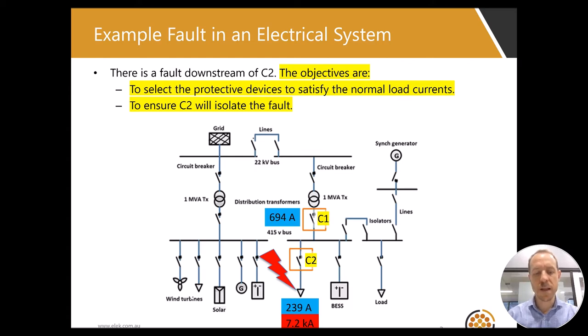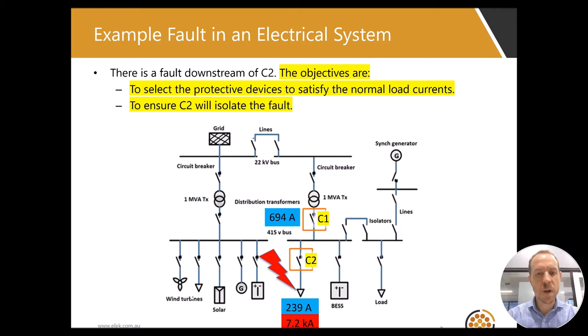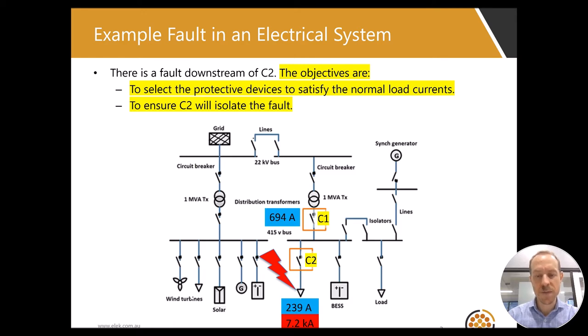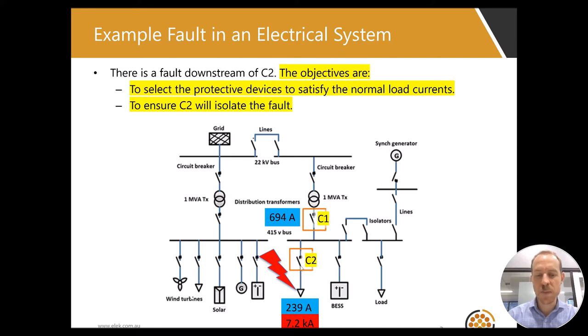Here is a schematic of an electrical system. In this example, I will focus on the selection of circuit breakers C1 and C2, and I will look at their discrimination for a fault on C2. The maximum normal operating current for C1 protected feeder is 694 amps, and for C2 it's 239 amps. The maximum prospective fault current for C2 is 7.2kA.